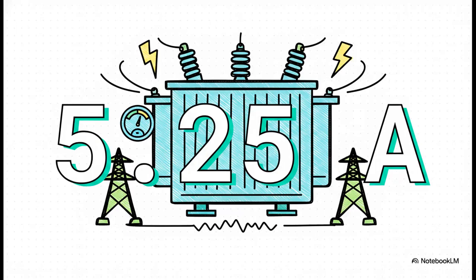Simple as that. So how do you know where to set that tripwire? Well, first things first, you've got to know what's normal. For a pretty typical 100 kVA transformer, that's just a measure of its power capacity, the normal, everyday operating current is right around 5.25 amps. This is its baseline, just doing its job.